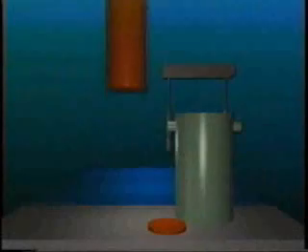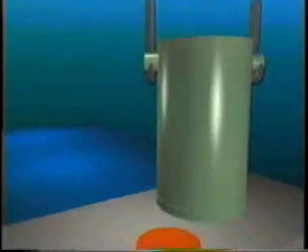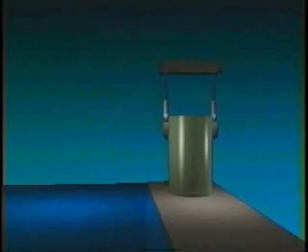Transferring the fuel from wet to dry storage begins by placing the empty fuel canister into a transfer cask that provides radiation shielding. The transfer cask, with the empty fuel canister inside, is lowered by crane into the spent fuel pool. One by one, the used fuel assemblies are placed in the fuel canister. After the fuel canister is loaded and still in the spent fuel pool, a shield lid is placed on top of the fuel canister. The fuel canister and transfer cask are then removed from the pool to a special area where the fuel canister is decontaminated, the shield lid is welded, and then the canister is vacuum dried and filled with inert helium gas through ports that are later sealed.